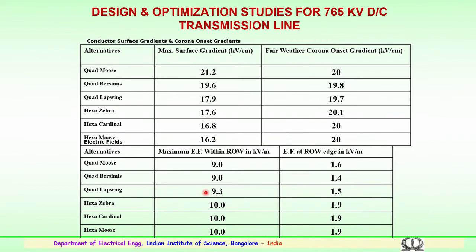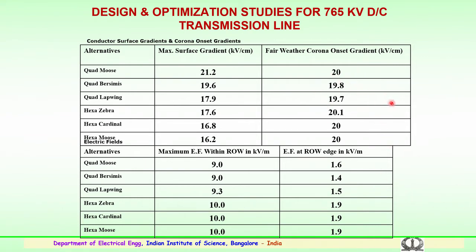Design and optimization carried out for 765 kV double circuit transmission line gives values of maximum surface gradient in kV/cm and fair weather corona onset voltage in kV/cm. For various conductor alternatives — quad moose, quadruple Bersimis, quadruple lapwing, hexagonal 6-conductor zebra, 6-conductor cardinal, and hexagonal moose — surface gradient studies show values from 21.2 to 16.2 kV/cm. Corona onset gradients were seen to be anywhere between 19.7 to 20.1 kV/cm.